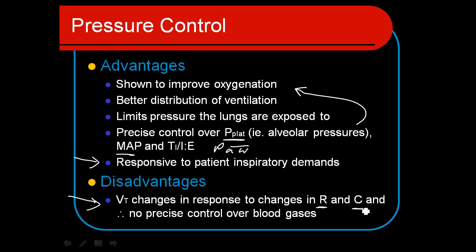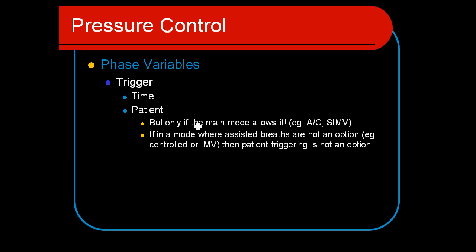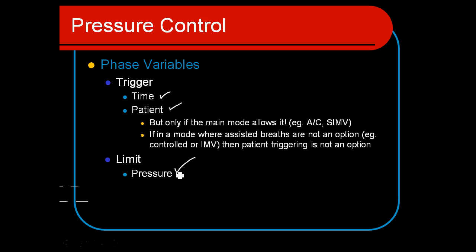The disadvantages are that we don't have direct control over tidal ventilation or minute ventilation. Changes in patient compliance will change the tidal volume, and thus we don't have as direct control over blood gases as we do with volume ventilation. The resistance doesn't usually change much since it's largely the resistance of the endotracheal tube, but lung compliance can change with disease. For phase variables, the trigger can be time or patient triggered, but the limit is always pressure limited and it is always time cycled.